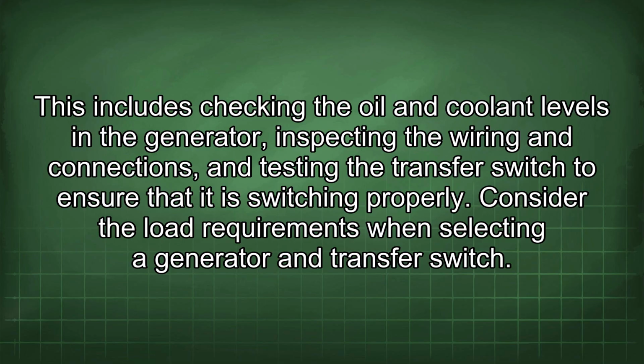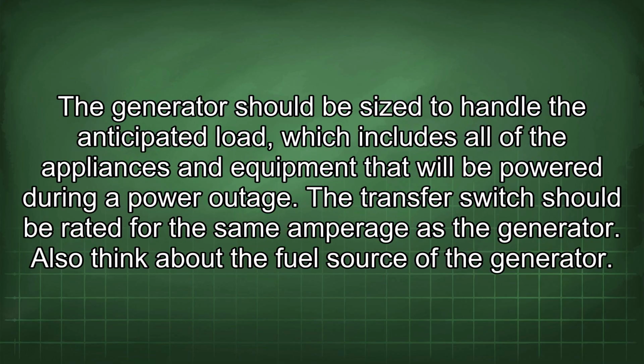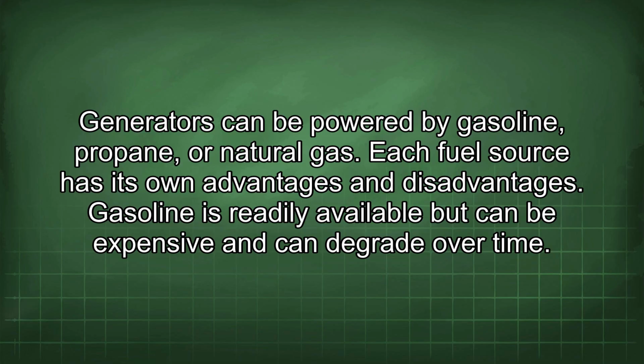Consider the load requirements when selecting a generator and transfer switch. The generator should be sized to handle the anticipated load, which includes all of the appliances and equipment that will be powered during a power outage. The transfer switch should be rated for the same amperage as the generator. Also think about the fuel source of the generator. Generators can be powered by gasoline, propane, or natural gas. Each fuel source has its own advantages and disadvantages.